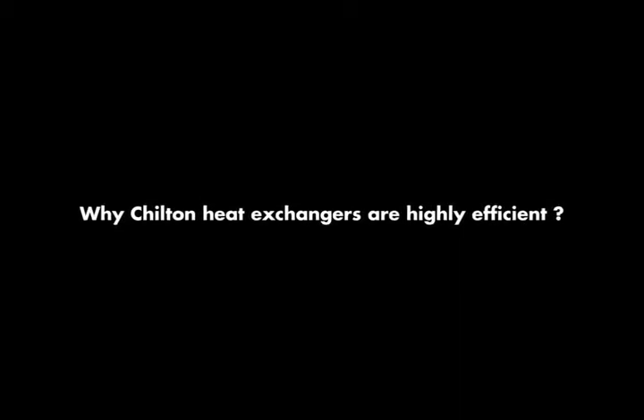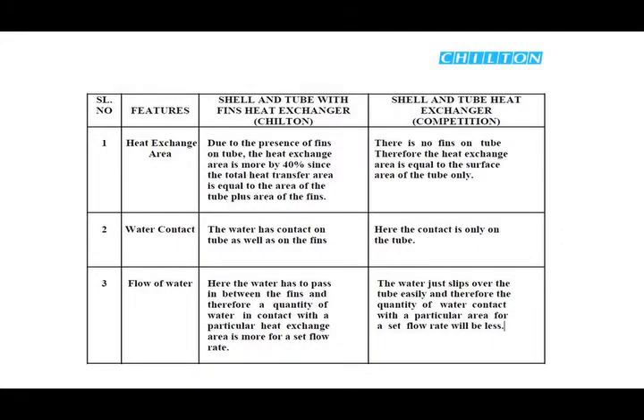Why Chilton heat exchangers are highly efficient. A comparative study of the features of the Chilton shell and tube with fins heat exchanger and the competition's shell and tube heat exchanger. Heat exchange area, Chilton: due to the presence of fins on the tube, the heat exchange area is more by 40%, since the total heat transfer area is equal to the area of the tube plus the area of the fins. Competitor: there are no fins on tubes, therefore the heat exchange area is equal to the surface area of the tube only.